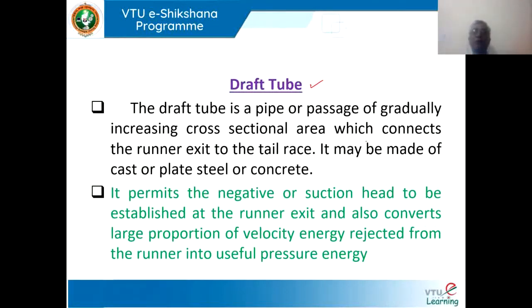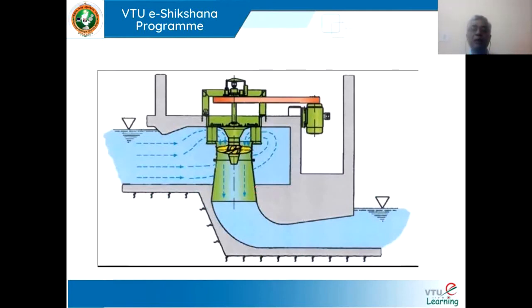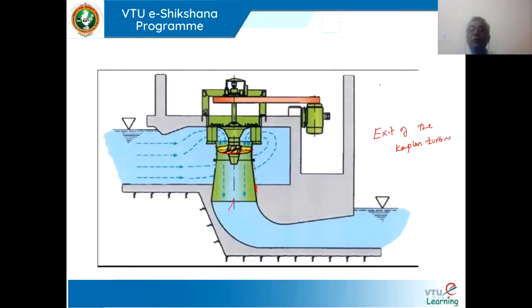The draft tube is connected to the end of the Kaplan turbine — at the exit of the runner. The draft tube is a gradually expanding pipe, conical in shape with enlarging diameter at the exit. The purpose of the draft tube is to decrease the velocity as the water flows out, so that the pressure increases. This increases the efficiency of the turbine.